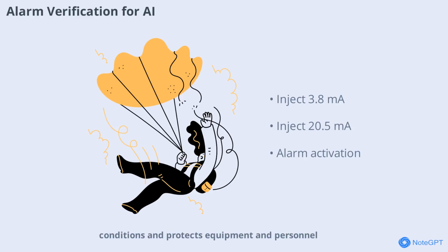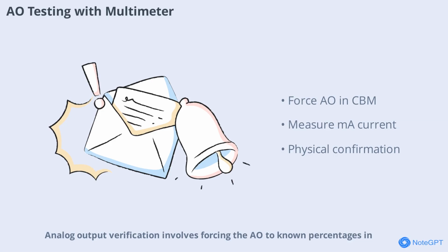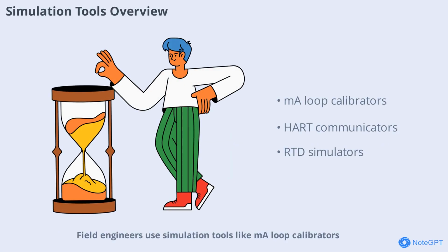equipment and personnel. Analog output verification involves forcing the AO to known percentages in CBM and measuring the mA current in the loop with a multimeter. The field engineer confirms that the valve or VFD moves to the correct position or speed, ensuring accurate control. Field engineers use simulation tools like mA loop calibrators, HART communicators, and RTD thermocouple simulators to test and verify signals. These tools enable engineers to simulate real-world conditions and ensure that the control system responds accurately.